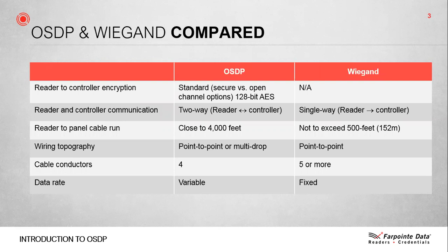OSDP provides for two-way communications. Wiegand is a one-way street for data. For example, this allows the reader to be queried as to its status — think about this as a health check, supervision, or sometimes referred to as a tamper. OSDP riding on RS-485 provides for longer cable runs, while Wiegand is shorter. Most Wiegand specifications only allow for 500 feet, whereas using OSDP with RS-485 you can go close to 4,000 feet. Wiring topography — OSDP offers optional configurations while Wiegand only offers one. This flexibility can be very beneficial in minimizing installation and retrofit operations.